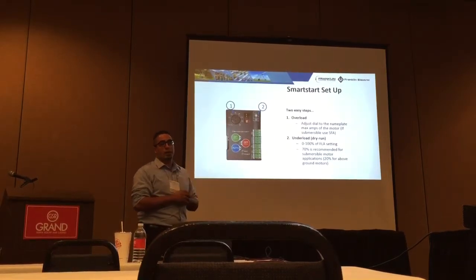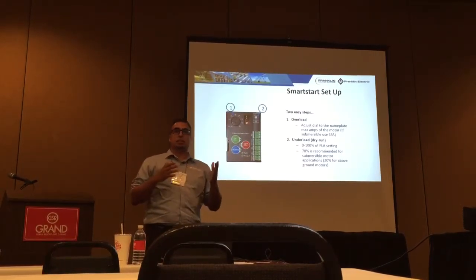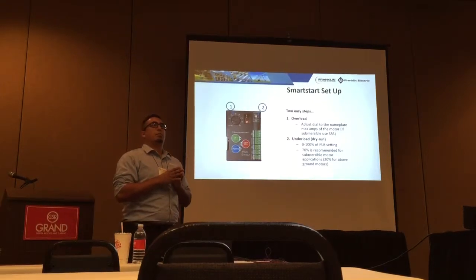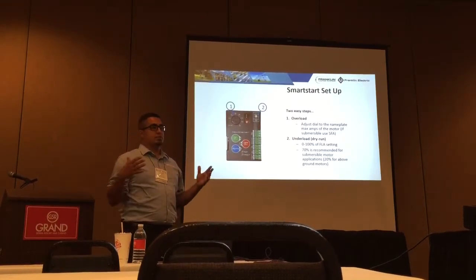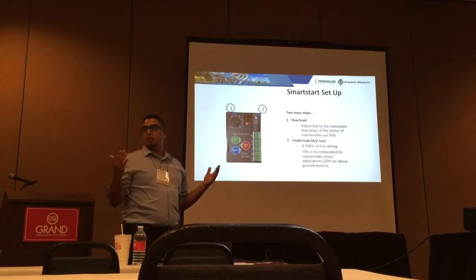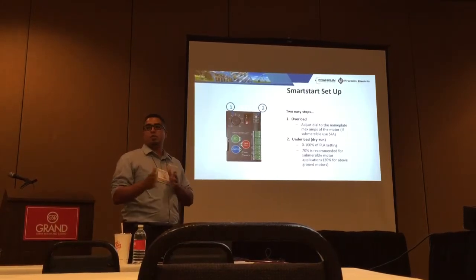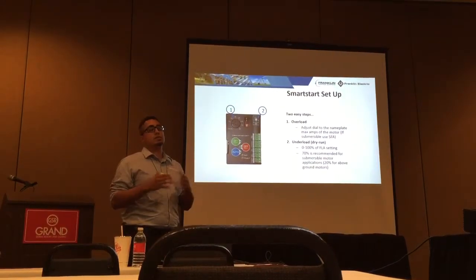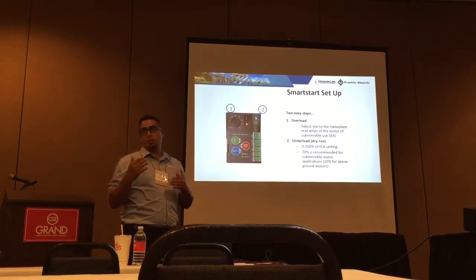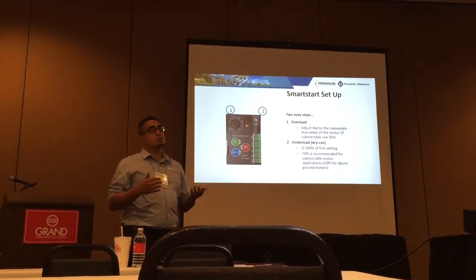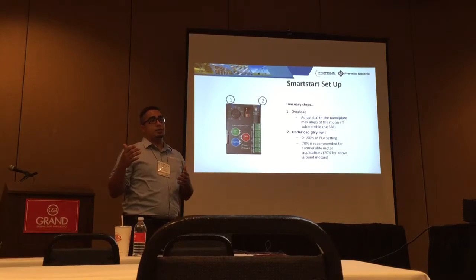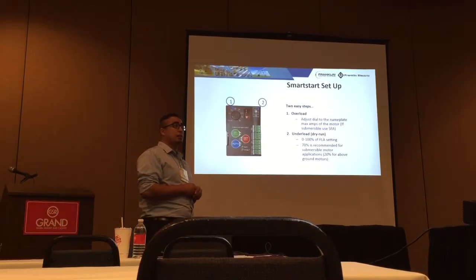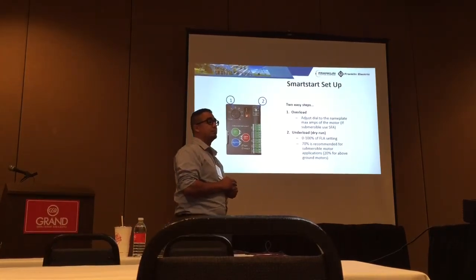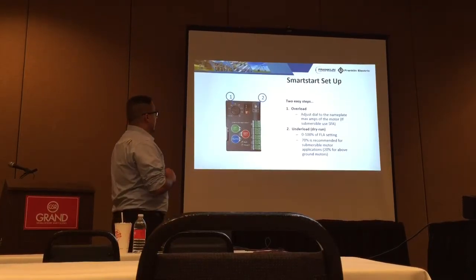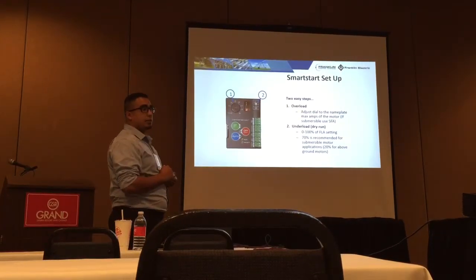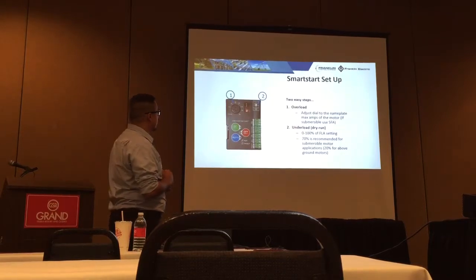That's one thing too that I'll point out is with the progression and the integration of the two companies, FLA and SFA, they've really progressed towards making sure everything pump related is service factor, both for surface and submersible. Some of the other products are labeled full load amps. Sure, I've just put in both and was kind of confused on some of them. Yeah, no, definitely. This is service factor. That's how the overload works on this one.